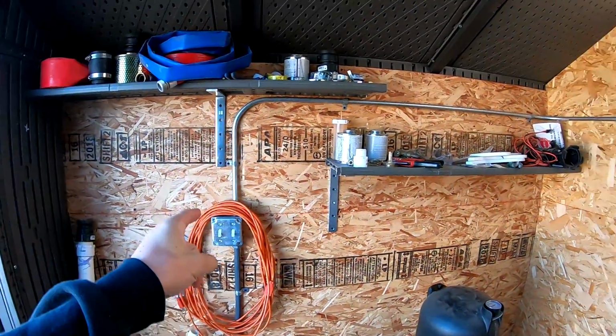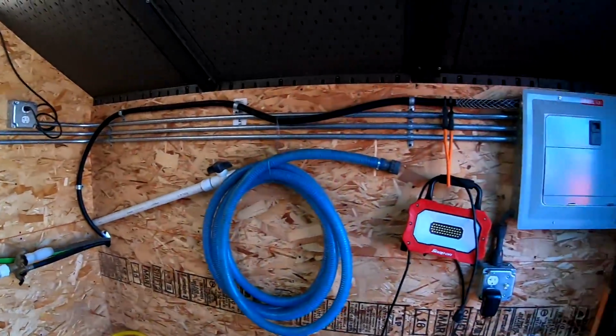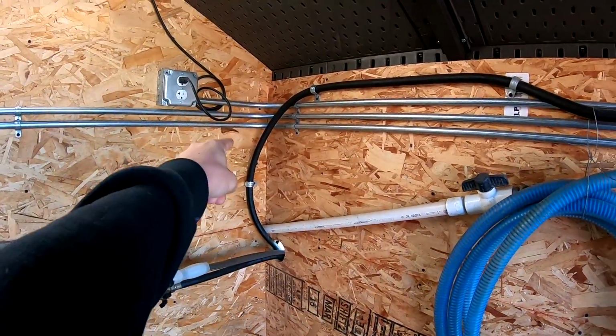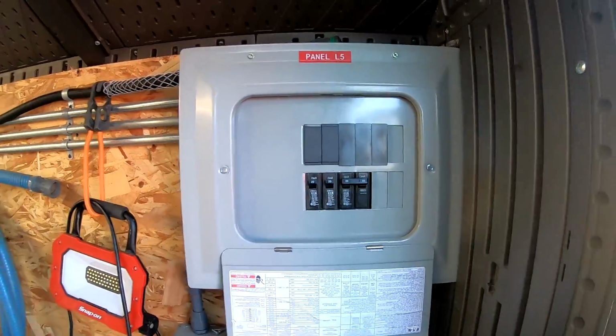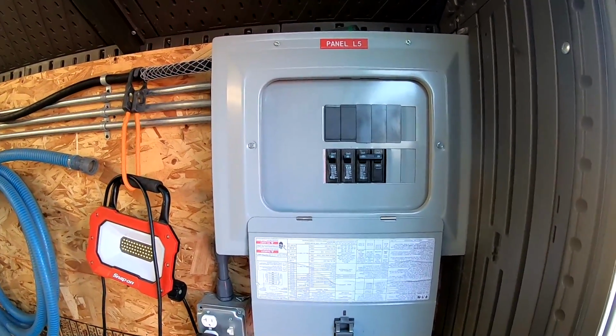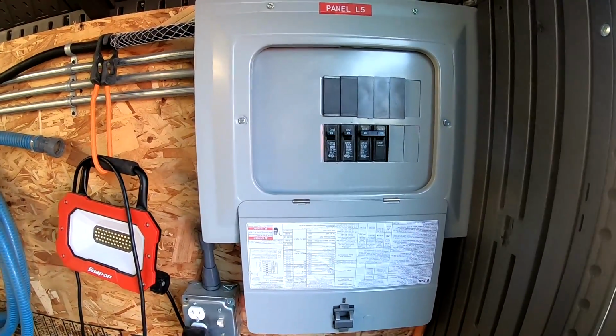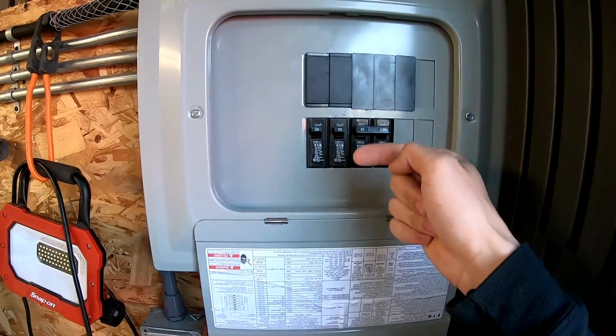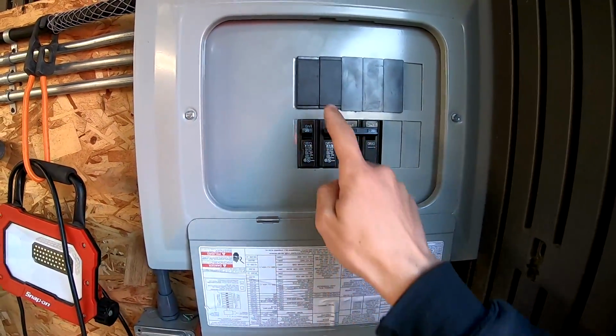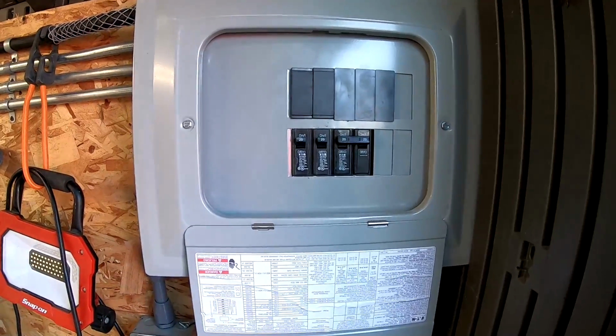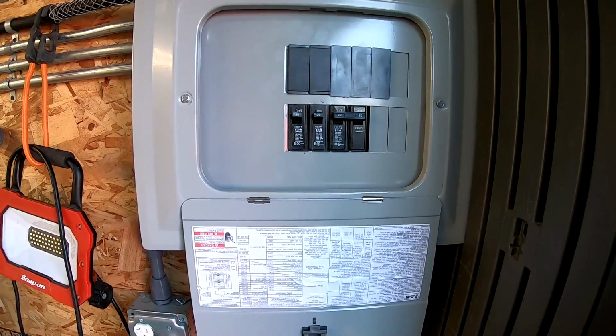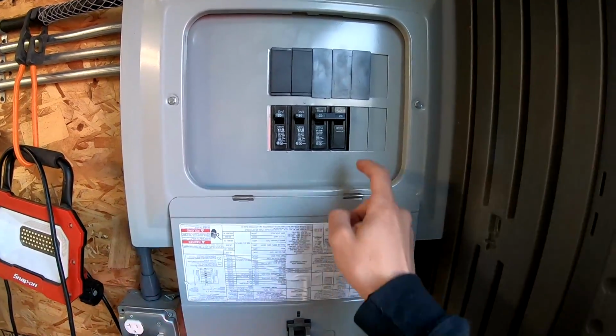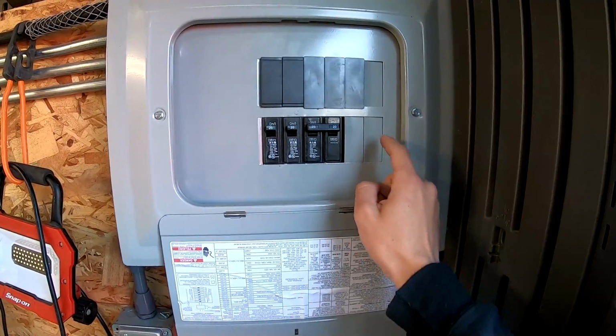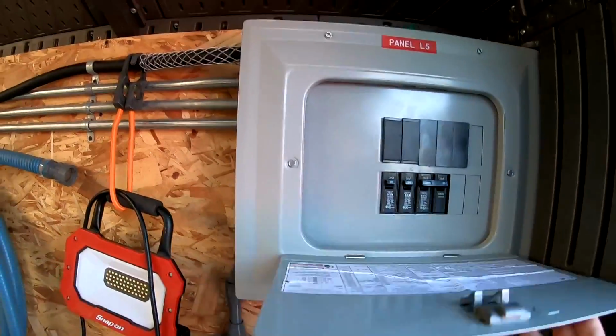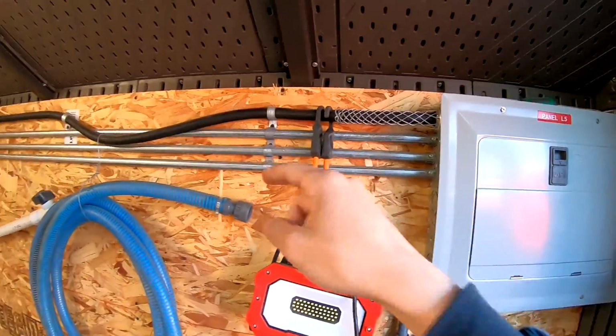This is wired in 1/2-inch EMT, and I have an SO cord coming in through here. That's this black one, and that comes into here, and you'll notice this is mounted horizontal. Now, one thing that is a thing in the code book is your breakers, the on, has to be up, not side to side. So this top row of this panel cannot legally be used in this horizontal configuration. I only have one or two more spaces I can use in this panel. But it comes out in these 3 pieces of EMT.